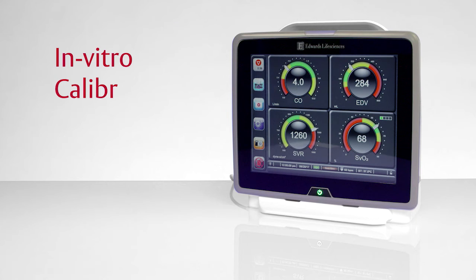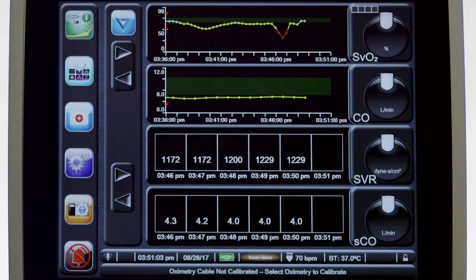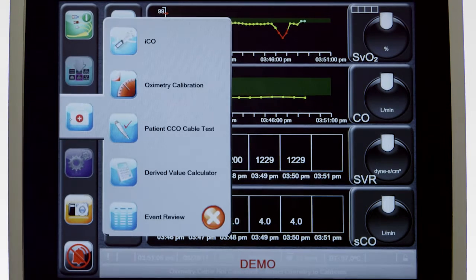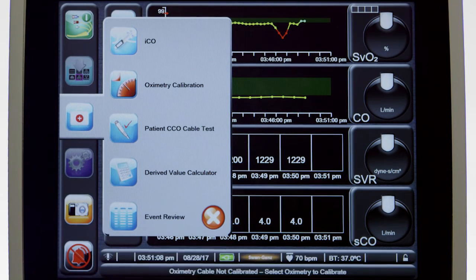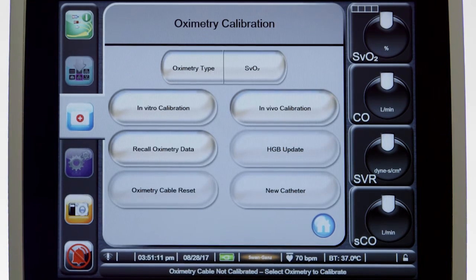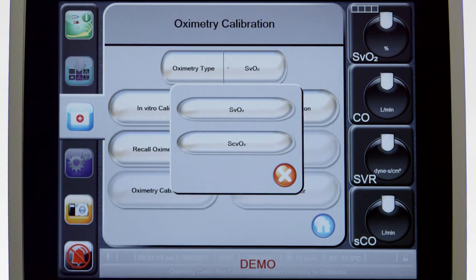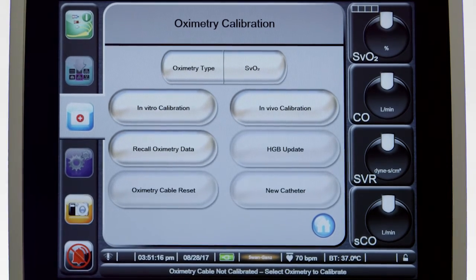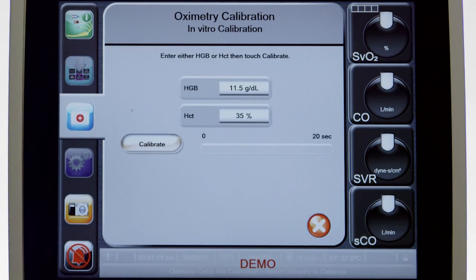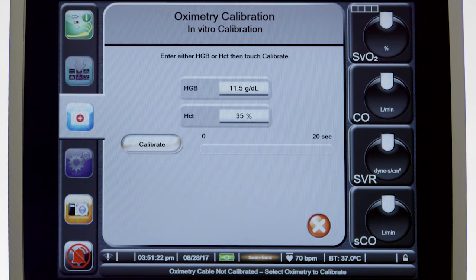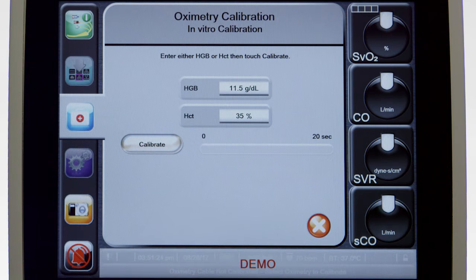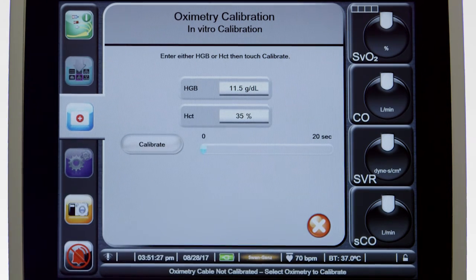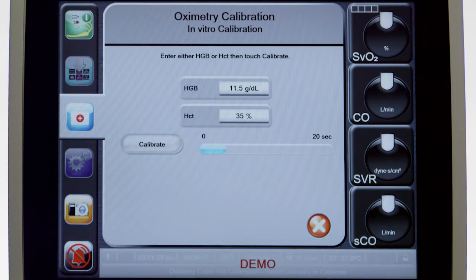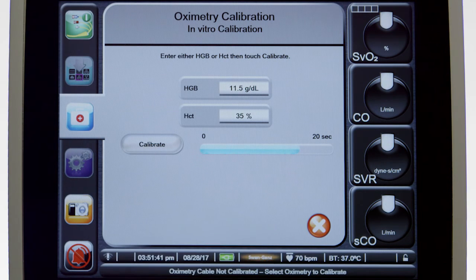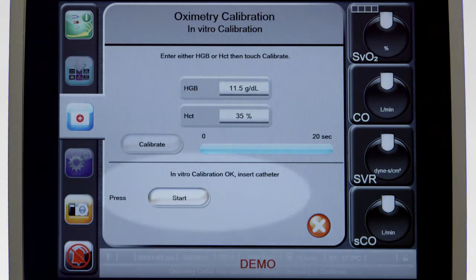In vitro calibration is performed on the catheter prior to its insertion in the patient's body. To begin the in vitro calibration, touch the Clinical Actions icon. Select Oximetry Calibration and confirm the oximetry type selected is SVO2. Touch In Vitro Calibration and enter your patient's hemoglobin value. The hematocrit value will be automatically calculated for you. Touch Calibrate and wait 20 seconds for the calibration to complete. When the calibration is complete, you will see the message, In Vitro Calibration OK, Insert Catheter.